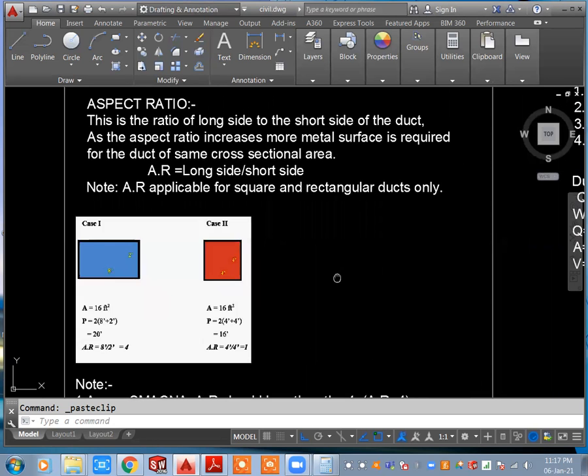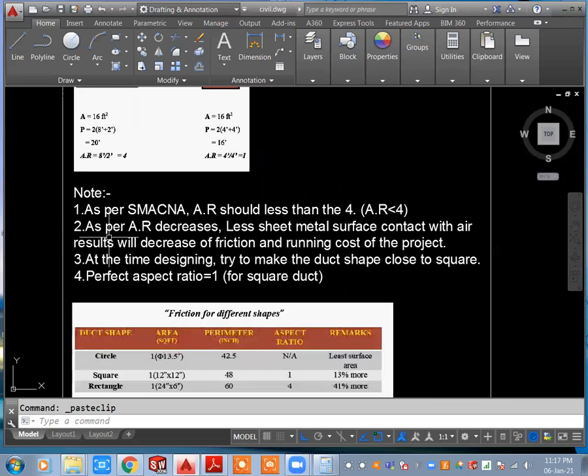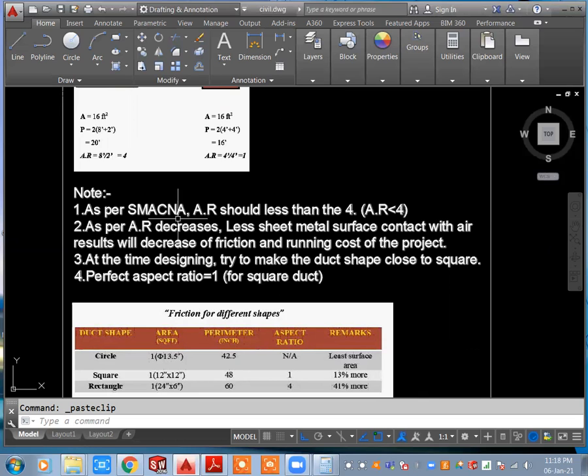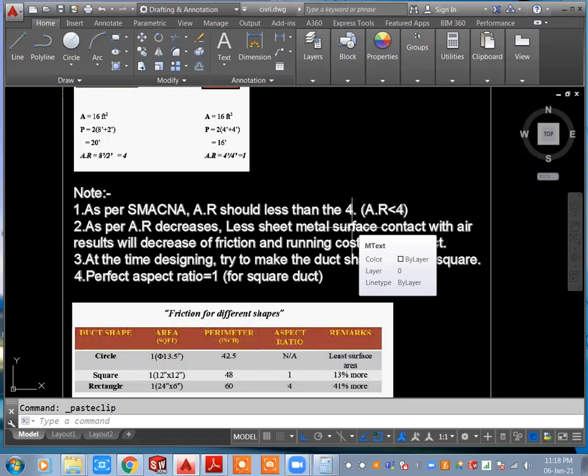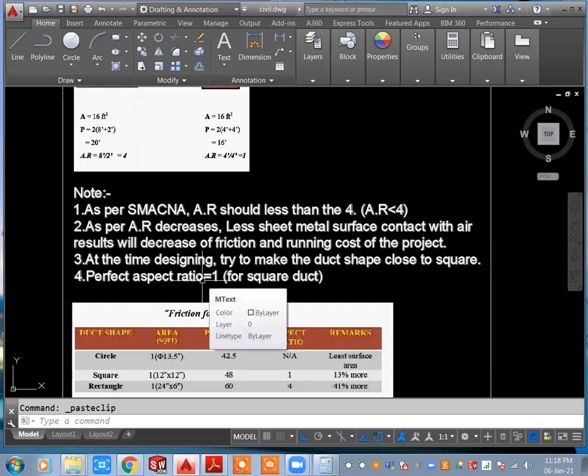Note: aspect ratio is applicable for square and rectangular ducts only. As per SMACNA — Sheet Metal Air Conditioning National Association — the aspect ratio should be less than or equal to 4. By maintaining this rule, you can balance your cost very easily and it is very helpful for clients.